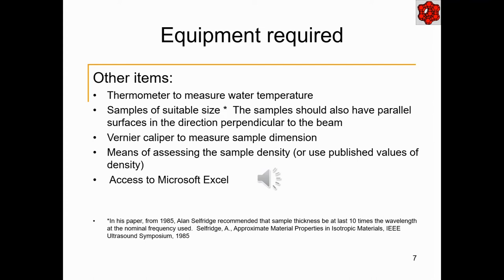Ultrasonic velocity is a function of temperature, therefore we are going to need a thermometer to measure the water temperature. Sample thickness is critical. To determine the thickness, we recommend a digital Vernier caliper capable of measurements to 0.01 mm. Once the data has been acquired, you are then going to need access to Microsoft Excel. Then you can use the template.